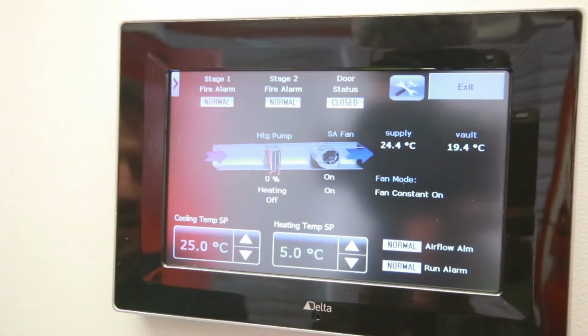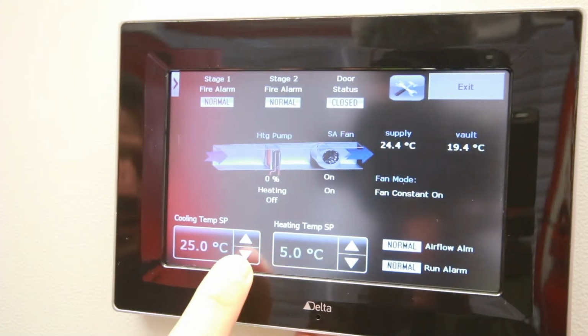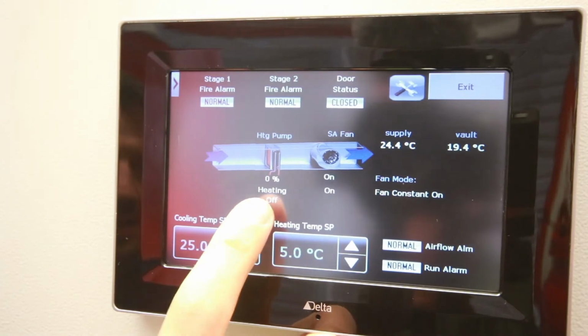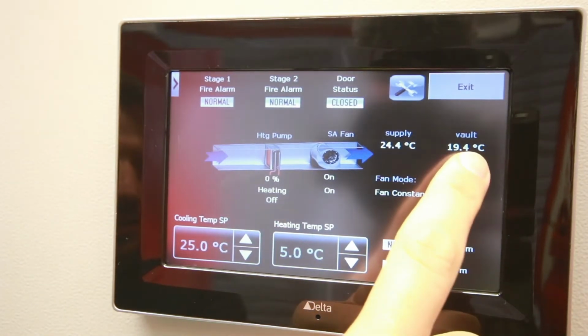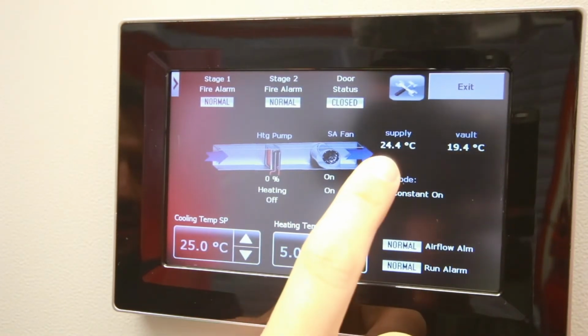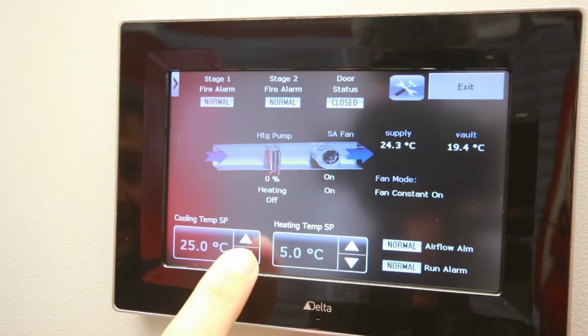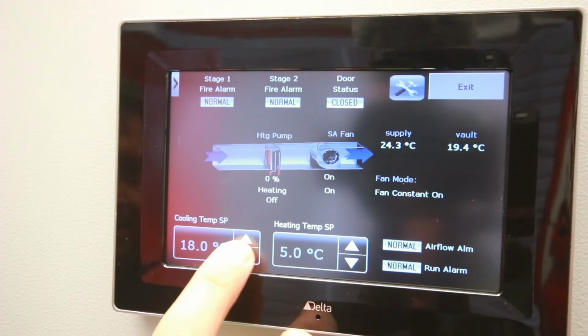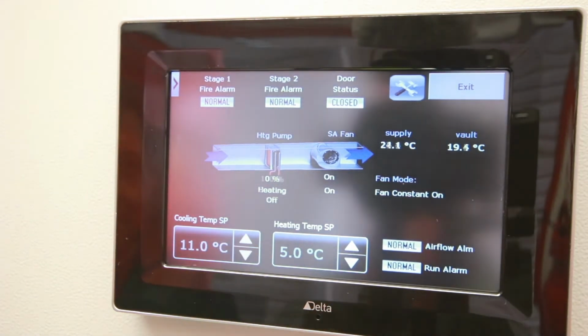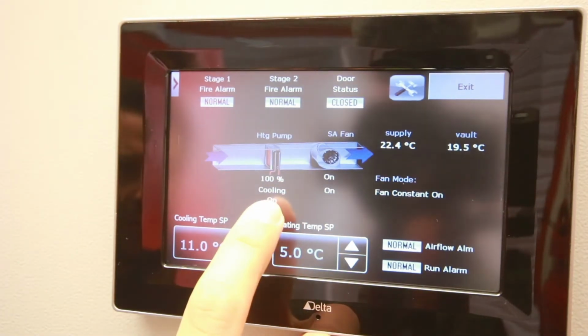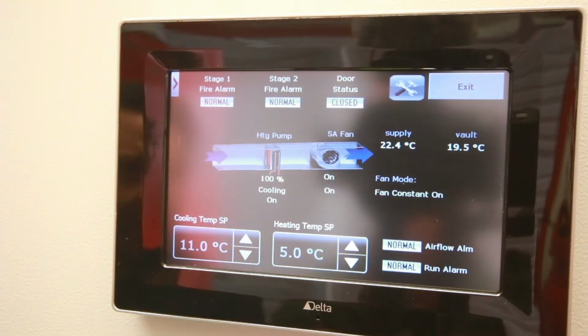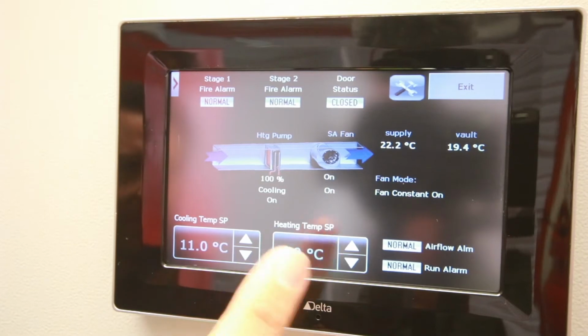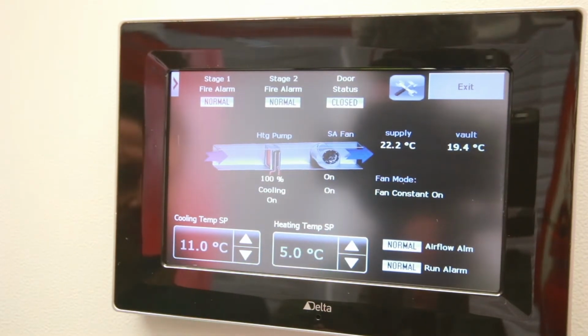In order to demonstrate the cooling effect inside the Firevault, we can adjust that here. You'll see currently the heating is off because our internal temperature is 19.4 and our supply air is above that. To kick in the cooling system, we can demonstrate this by reducing our cooling temperature set point. As you can see, this has now activated the cooling system, which is working at 100%, and it will try and reduce the temperature inside the store.